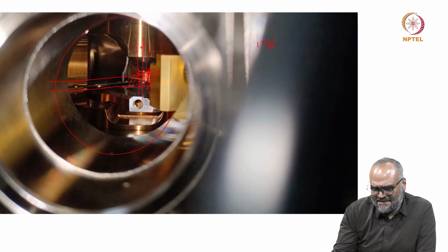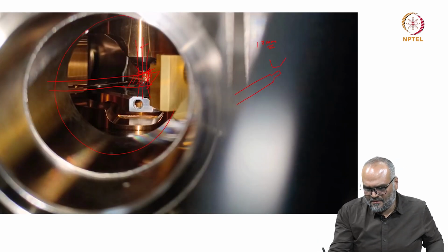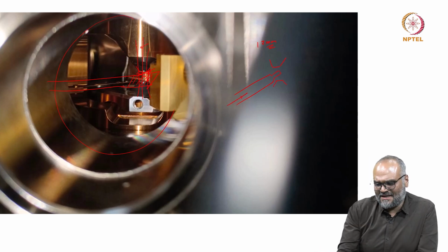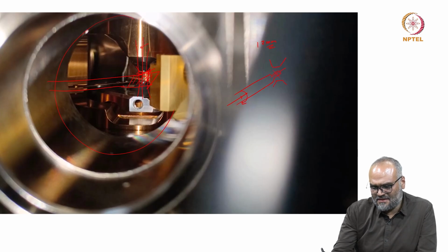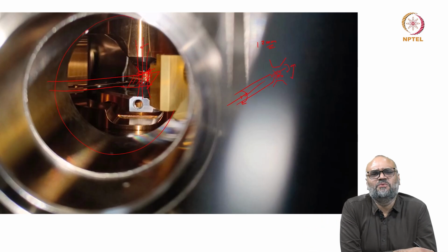So if my holder design is like this, and this goes into a gap between the lenses here, this electron microscope holder can either rotate along this axis or along this axis. So this rotation or this rotation are restricted by the gap I have within the pole pieces.